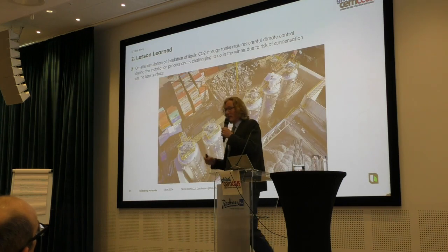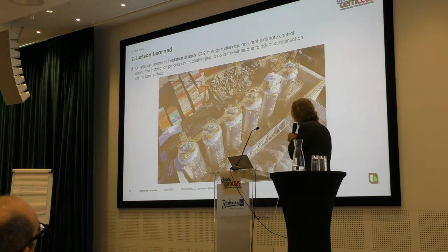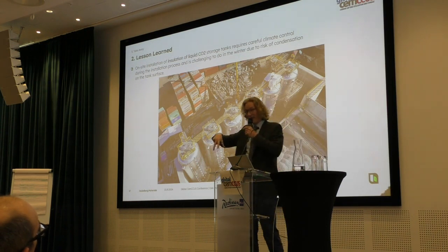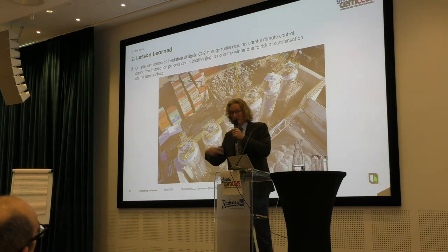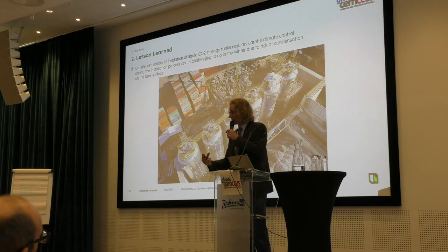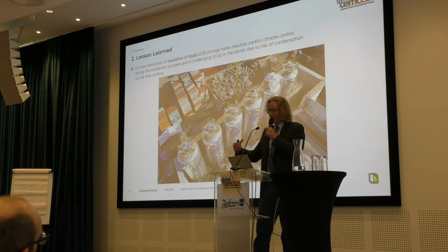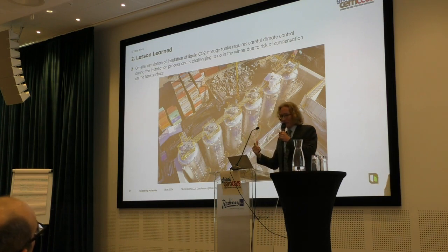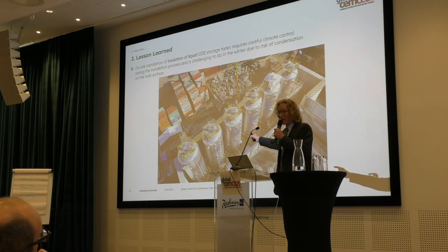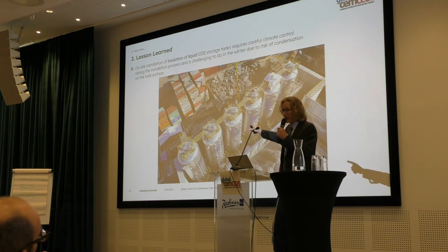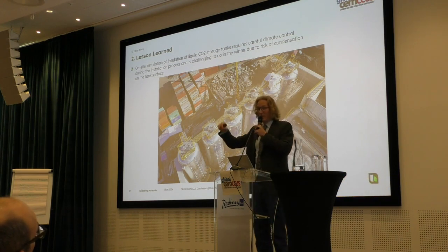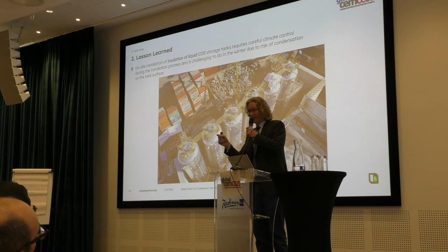Speaking again about the CO2 tank farm, they were delivered placed on cradles, and these cradles were not insulated because the insulation would have been damaged during transportation. So they had to be insulated on site. That's also something to think about. If you don't have a specialist on cold insulation, get one, just to make sure it's done correctly, because when these tanks are in operation, filled with liquid CO2 at minus 26 degrees, you don't want ice build-up between the steel and the insulation. That would be a big headache to repair.